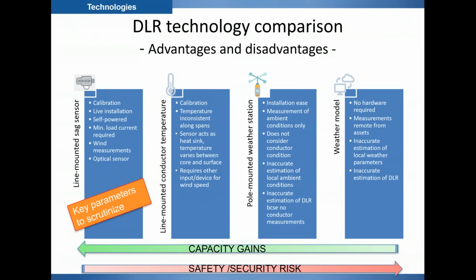And then finally, last but not least, you have other categories of sensors, which we're proud to supply, but we're not the only ones, which would be directly mounted on the line and would measure a whole range of parameters, the temperature as well, but the sag also directly. There are different methods to do it, and also the prevailing ambient conditions seen by the conductor itself, and notably the wind. So if you're able to do that, then you have all the input parameters to calculate an accurate DLR value, and therefore make full use of its gain, while remaining completely safe and secure, because you permanently monitor the temperature and the sag. So if ever something wrong was to happen, and if ever we were getting too close to the maximum limit, we could raise an alarm.